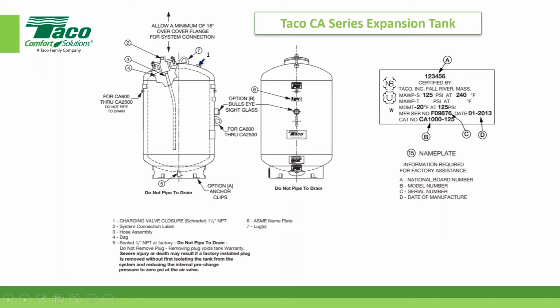Item 5—we're going to have another discussion from my high horse on this as well—do not pipe this to drain. If you look in this paragraph, removing the plug voids the tank warranty, so that plug should just stay there. That's only if the bag fails and you have to empty all the water out of the tank because the bag failed. You don't want to pipe that to drain, because invariably you take that cap off—first off it could be dangerous if you don't do it properly—and second, if you put a valve on there, as these tanks heat up and cool down...